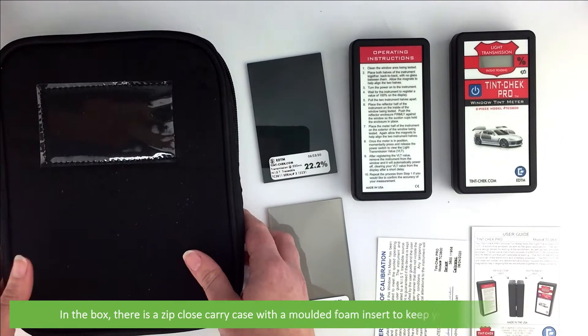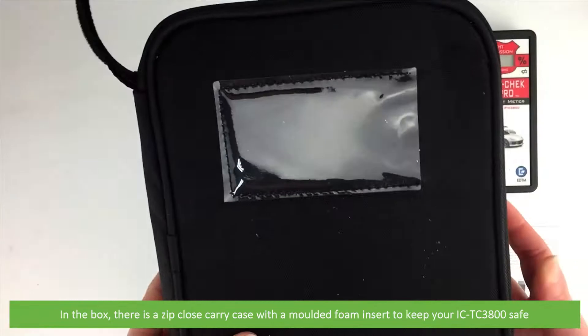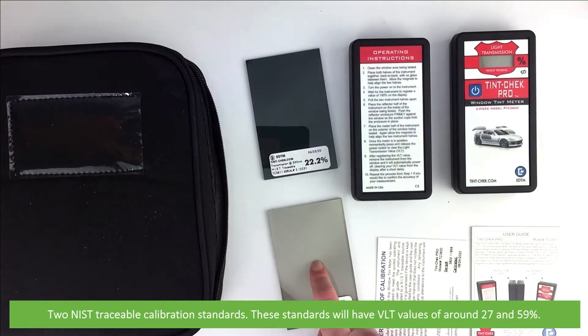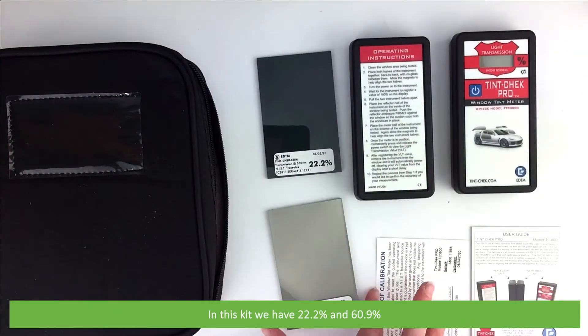In the box there's a zip-close carry case with a moulded foam insert to keep your IC-TC3800 safe. Two NIST traceable calibration standards. These standards will have VLT values of around 27 and 59 percent — in this kit we have 22.2 and 60.9.